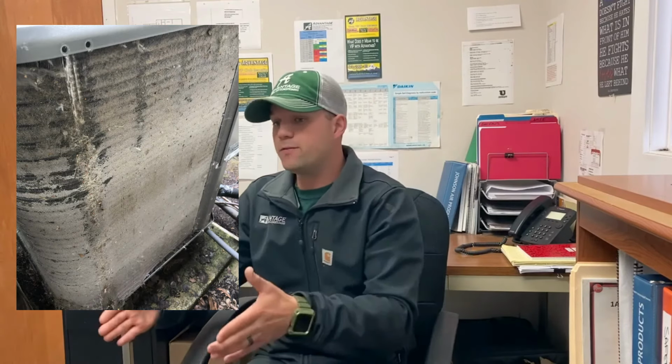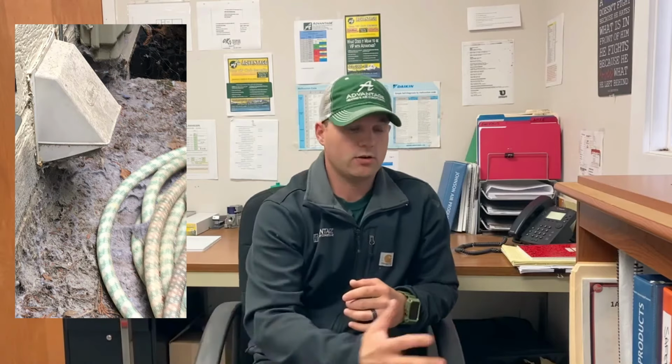Now, even if you had a maintenance on this system and your dryer vent is right next to your coil, it doesn't matter. You know, 3 months, 4 months down the road, it's going to get bad. And that dryer vent lint is going to suck right up onto that coil. So you want to make sure you do a walk around, look inside the coil and see if you have a bunch of lint. If you do, look and see where that dryer vent is terminating outside the house.